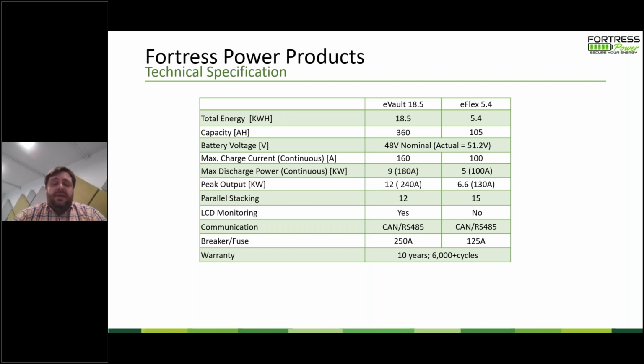The eVault has a screen on it. The eFlex doesn't. We do have tools to log into the eFlex battery and see the individual stats that are really used on commissioning and maintenance. Inside both batteries, you have disconnects, you have relay contactors, you have fuses. Most code does not require a specific overcurrent protection or a specific disconnect for these 48-volt battery systems. Nonetheless, on the eVault, you have a double pole breaker, 250 amps that goes on and off. The eFlex has a push button rather than a breaker because it helps the eFlex maintain that IP65 weatherproof case. It's a little bit more rugged of a design factor.